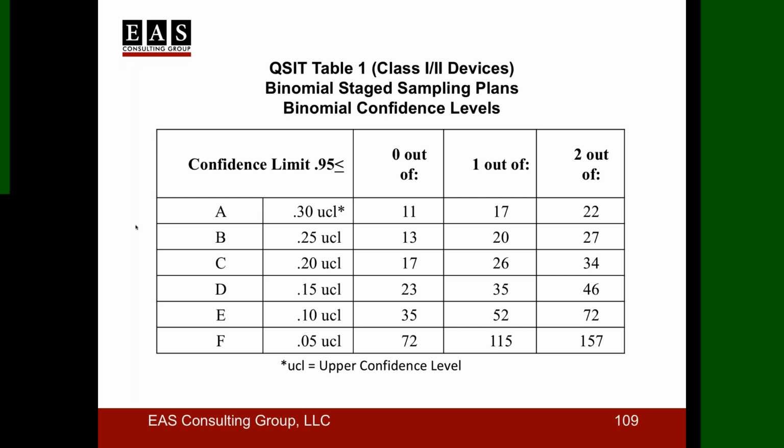So you say, oh, I have 300 complaints. Since that is over 30 total, they're going to use the sampling table. If it's 30 or less, they're going to look at all of those complaints for that 2-year time period. So if it's over 30, they can pick from in between 11 to 157 of those 300 records.